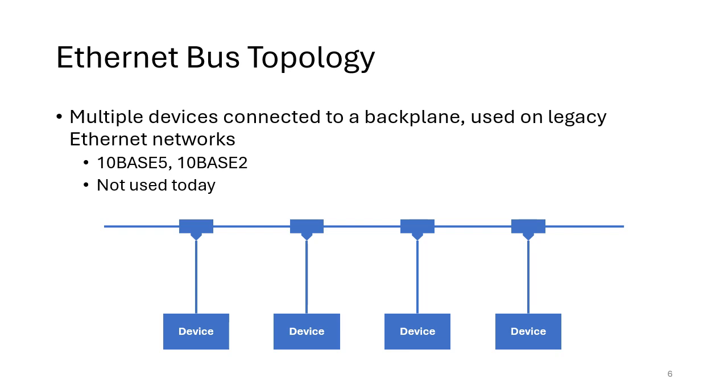In practice, it was quite complicated to use because you needed to use the connectors, you needed terminations at the end of the network, which were actually physical devices themselves. If a termination was wrong, or the connections were badly made, or possibly if a single device failed, or certainly if a single cable failed, then the network would fail. Also, if the termination was wrong or removed, again, network failure or reduced communication speed. So great technology in its day, but wouldn't really be seen today.